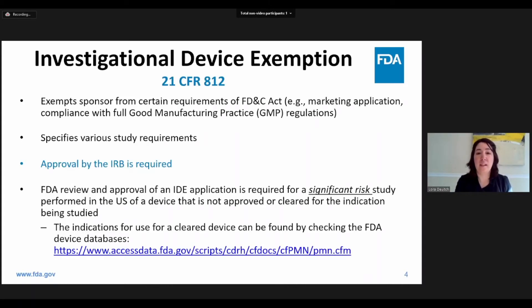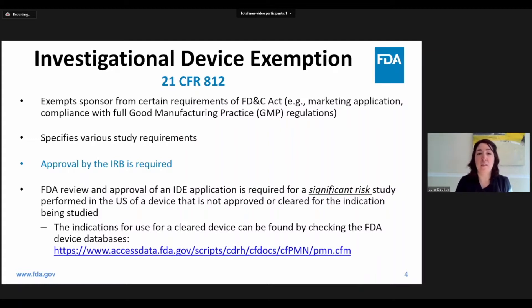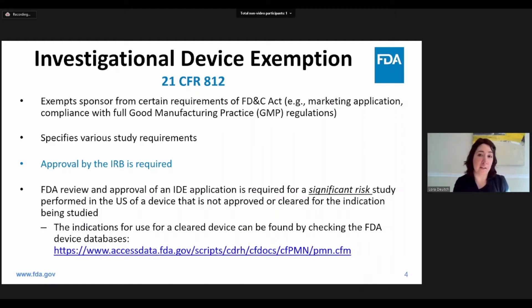IDE stands for Investigational Device Exemption. The IDE regulations provide procedures for the conduct of clinical investigations of devices. They explicitly describe study requirements such as those for informed consent, labeling, monitoring the study, keeping records, and submitting reports. Initiation of a clinical investigation involving human patients, which is subject to the IDE regulations, also requires approval of the investigation by an IRB before initiation of the study.